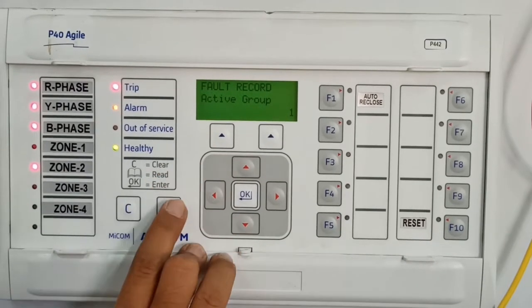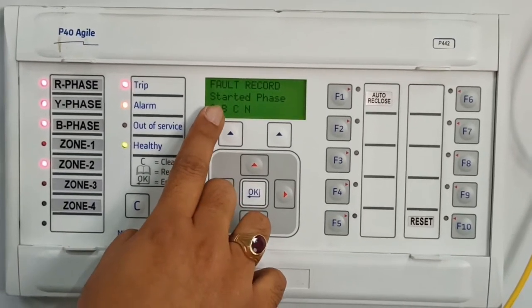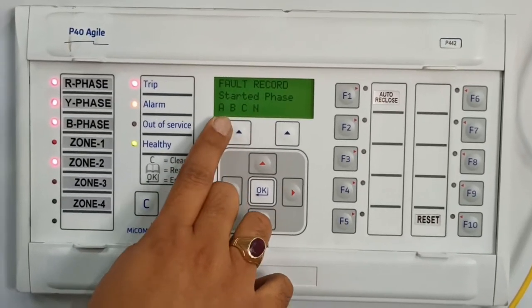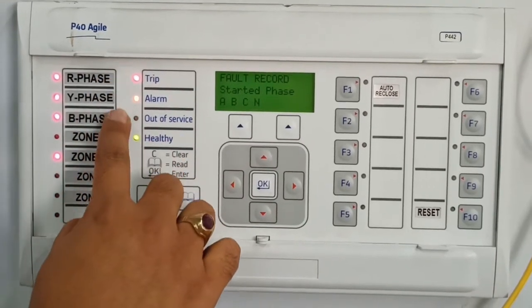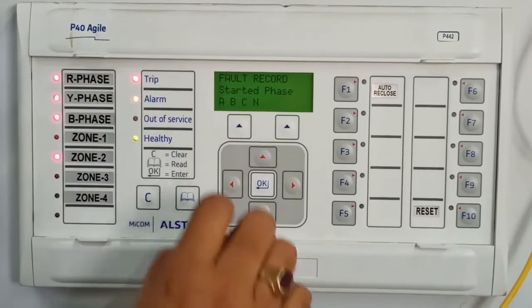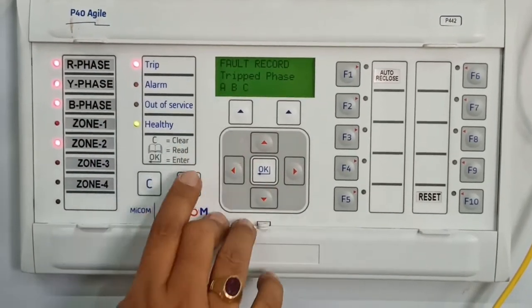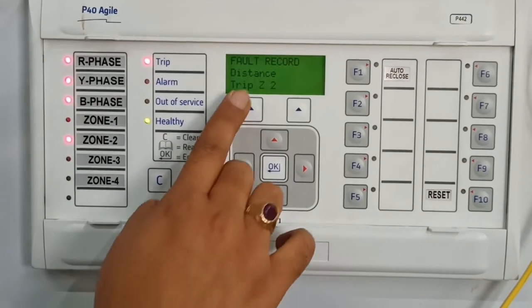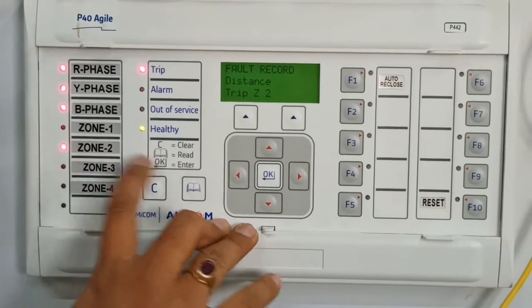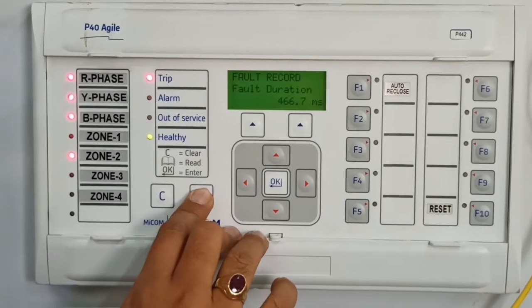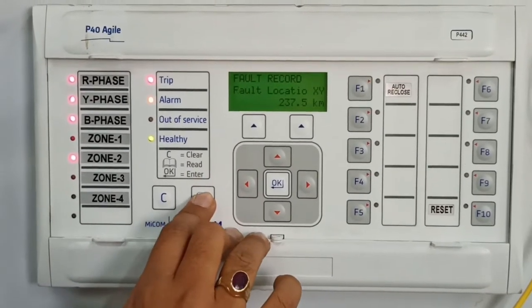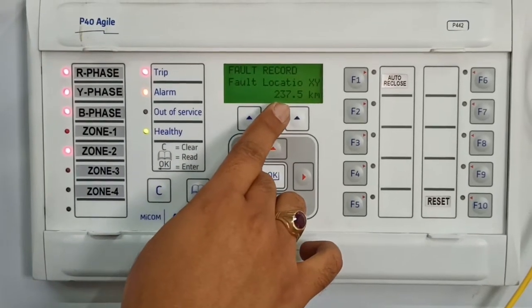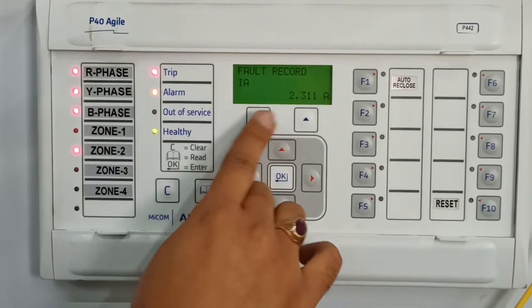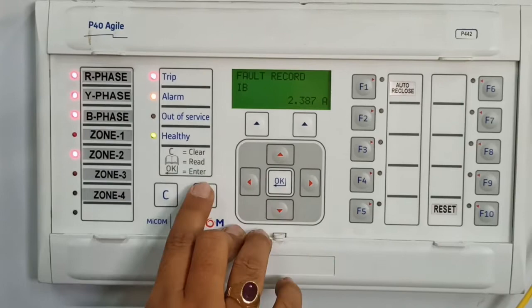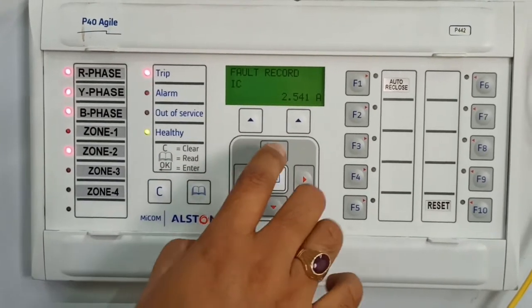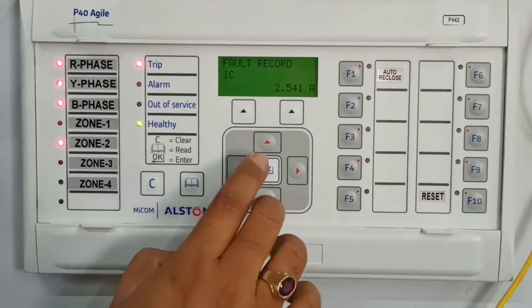Here the active group is 1, and the started phase is ABCN. We have made the triple line to ground fault, that's why ABC means RYB. Then the trip phase is ABC, the distance trip is zone 2, and the fault location is 237.5 kilometer. IA is 2.3 ampere, IB is 2.38 ampere, and IC is 2.5 ampere. The fault is happening on all three phases and ground, that's why all the currents are high here.